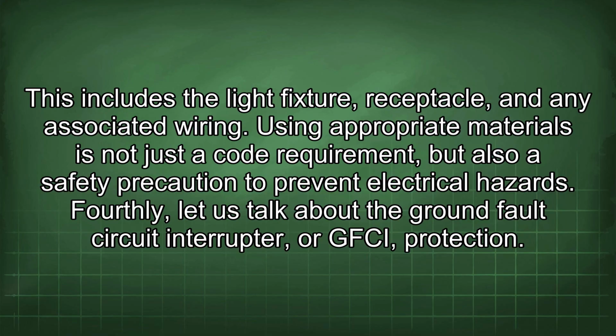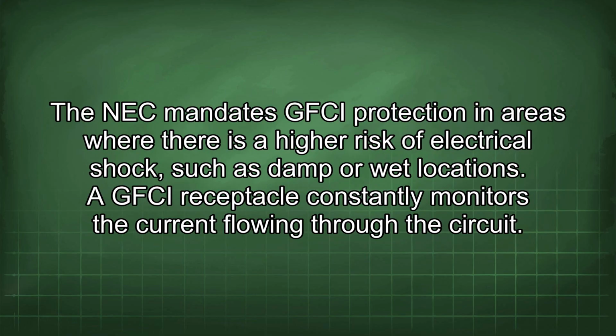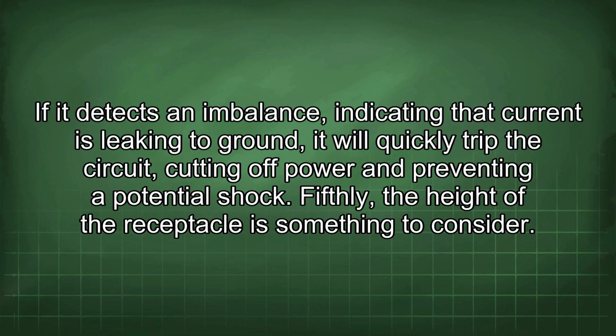Fourthly, let us talk about the ground fault circuit interrupter, or GFCI, protection. The NEC mandates GFCI protection in areas where there is a higher risk of electrical shock, such as damp or wet locations. A GFCI receptacle constantly monitors the current flowing through the circuit. If it detects an imbalance, indicating that current is leaking to ground, it will quickly trip the circuit, cutting off power and preventing a potential shock.